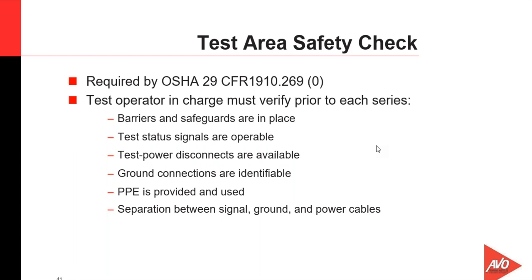Ground connections are identifiable, PPE is provided and in use and has been inspected prior to use, and we separate our signal, ground, and power cables where we're using high current surge cables and high voltage cables. The requirement here is that signal or instrument cables would be separated from ground and power cables and not just all coiled together or twined together, which could cause spurious signals in the sensing circuits of some of the test equipment.